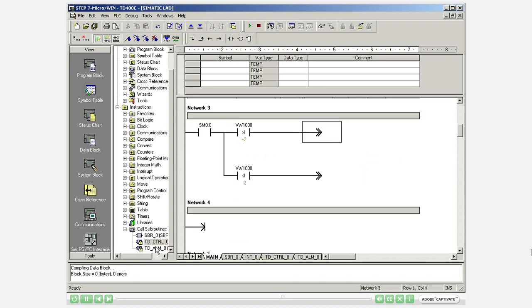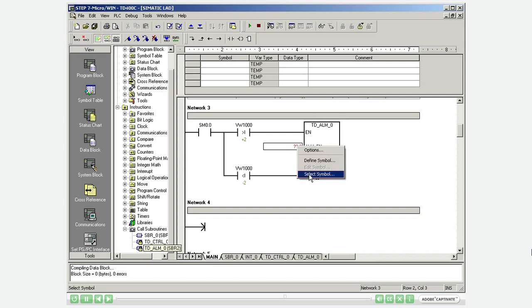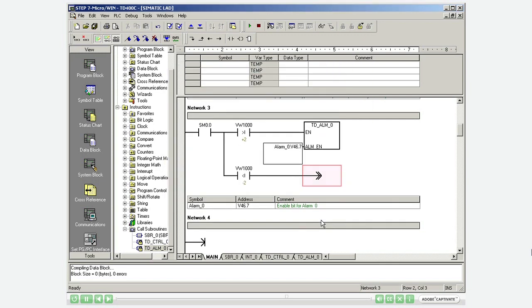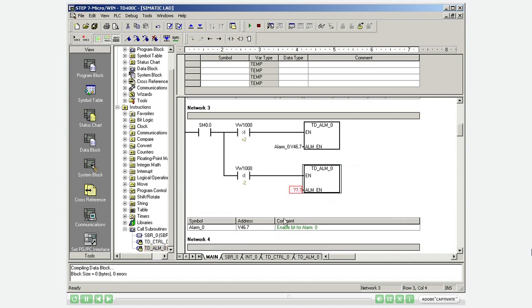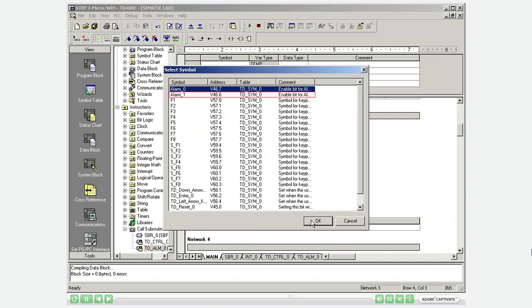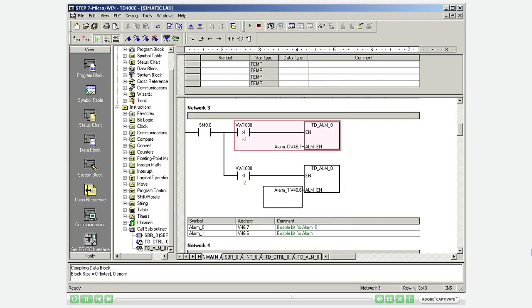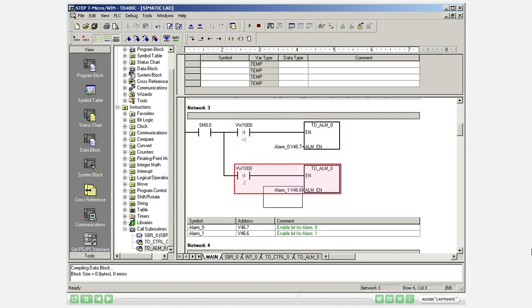Program the alarm calls in Network 3. You find the corresponding alarm addresses by right clicking and selecting the symbol. If the value of VW1000 is greater than 2, alarm 0 will be activated. If it is less than minus 2, alarm 1 will be activated.